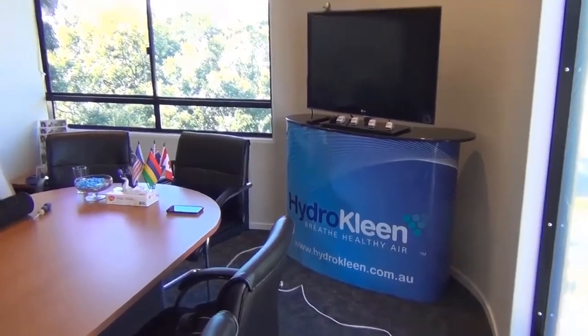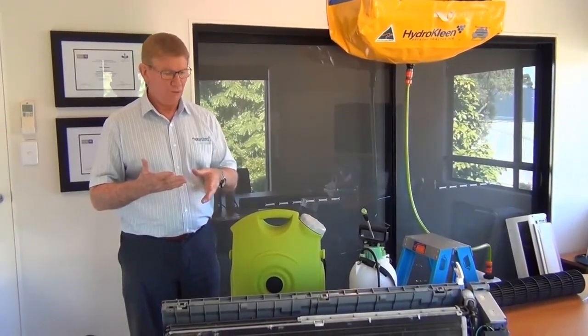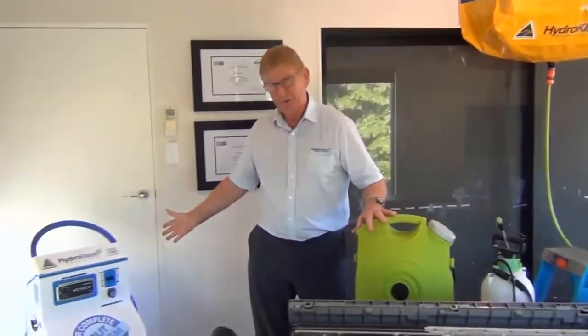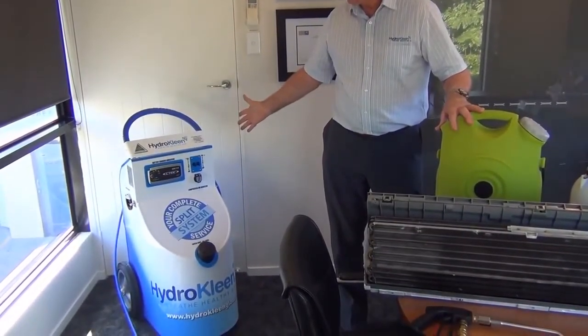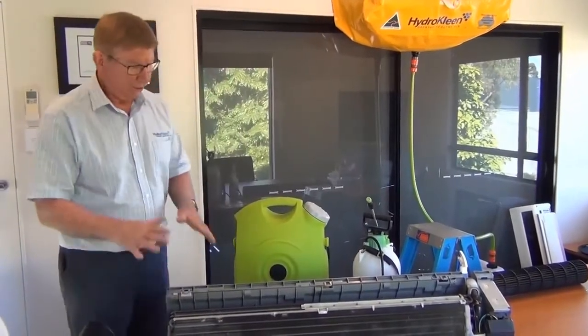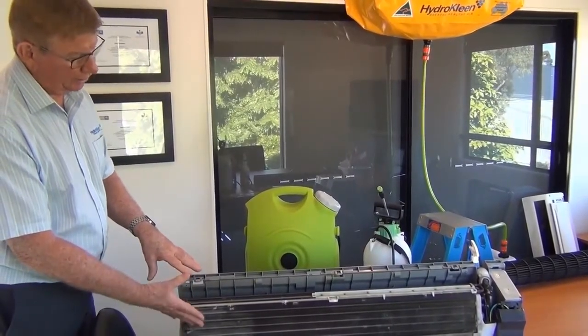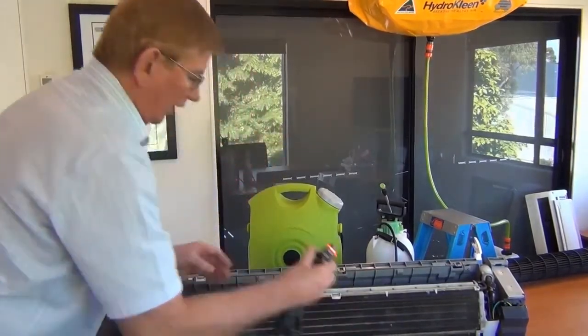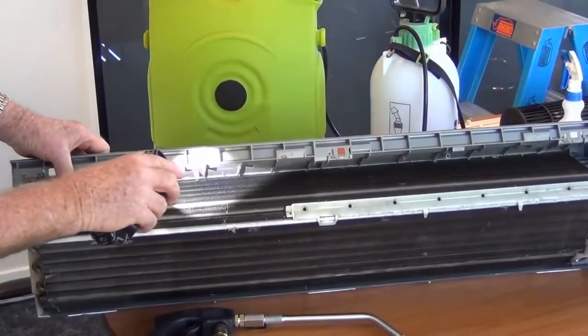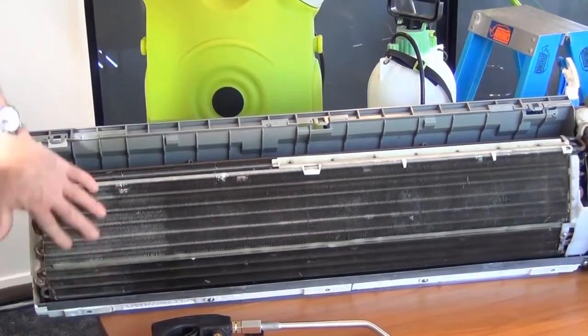Here we are in our training room at head office. I thought we would just use a live air conditioner to show you some of the differences between what HydroKleen can do and what this sort of equipment here can do. You can see our HydroKleen machine here that is purpose-built to clean domestic type air conditioners and we now sell them all around the world. One of the major problems with cleaning air conditioners nowadays is that the manufacturers have built a lot of coil that runs down the back — actually about a third of the evaporator coil that you can't even see from the front.